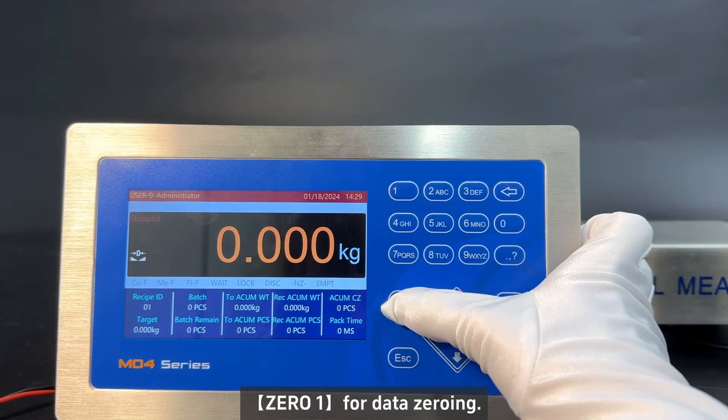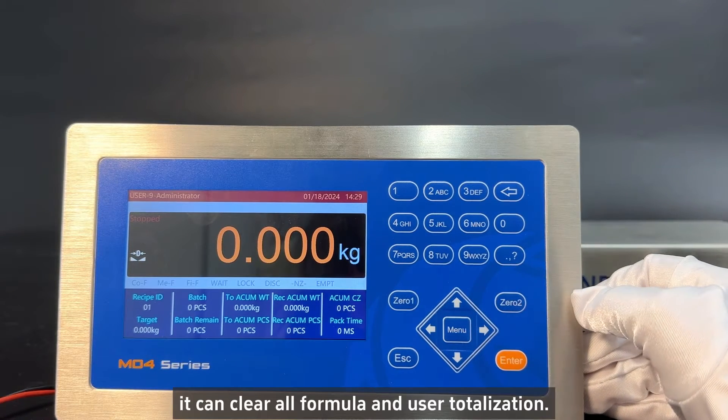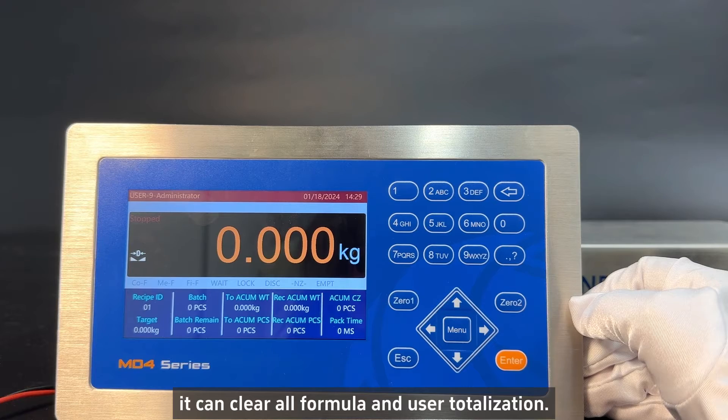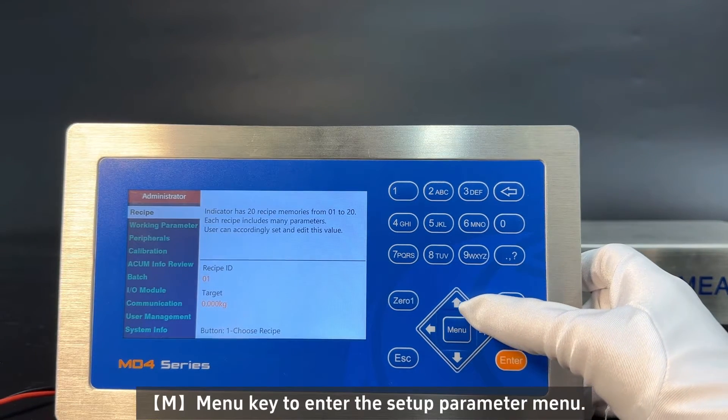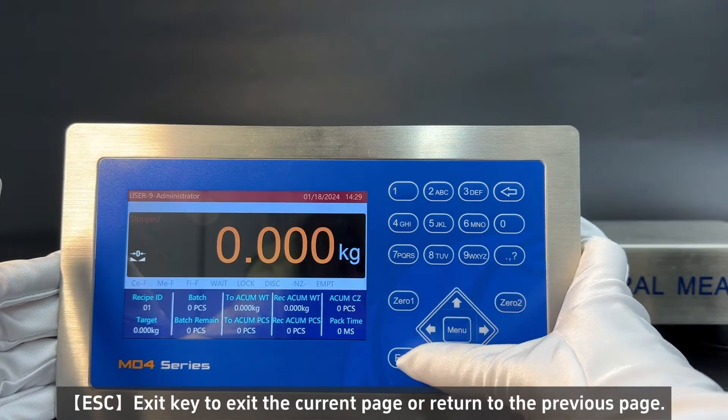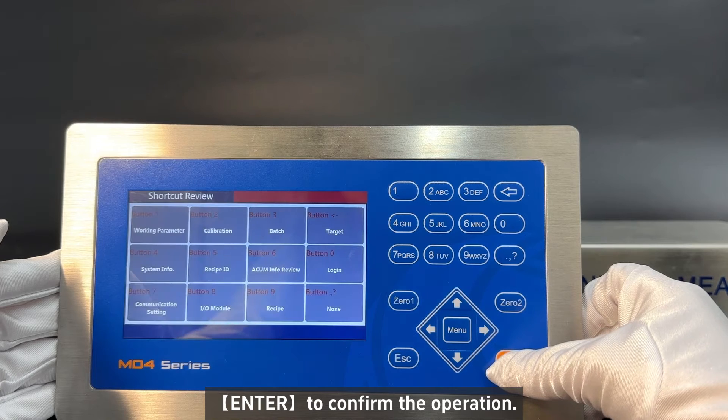Zero 1 for data zeroing, Zero 2 in the totalization interface can clear all formula and user totalization. M-menu key to enter the setup parameter menu. ESC exit key to exit the current page or return to the previous page. Enter to confirm the operation.